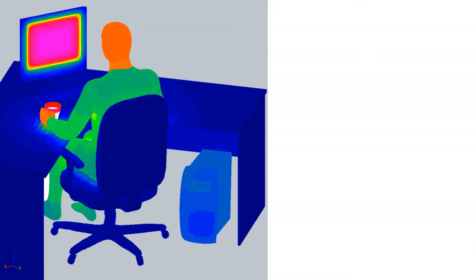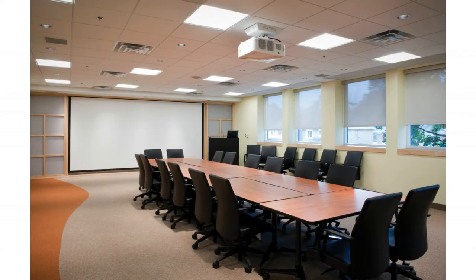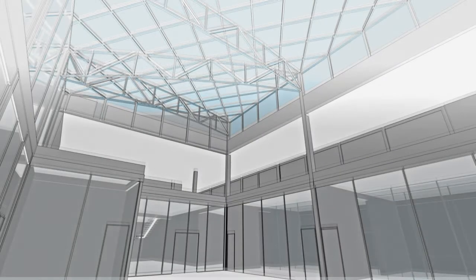Based on this, the occupants enjoy greater freedom in the selection of clothing, no fear from draft and icy airstreams in cooling mode. CO2 sensors are mounted in the space such as conference rooms or break rooms, as the standard specifies, to maintain the comfort conditions when the space occupancy rate is high. The corridor surrounding the atrium on the first floor shares the same airspace with the ground floor atrium space. Therefore, it's necessary to maintain a higher pressure in the corridor to avoid incidence of the hotter and polluted air from the upper layers of the atrium.